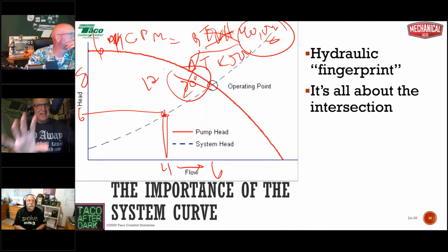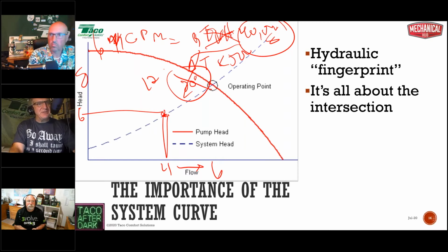That's the danger of oversizing. And with that 3-speed pump, the urge to oversize is huge. We go right to contractor no-callback mode and get out of there. Nobody calls us to complain that they're cold, so we think we've done a good job, except we've reduced and intentionally limited the efficiency of the system. And we've put all of the moving parts on notice that we're going to wear them out ahead of time.